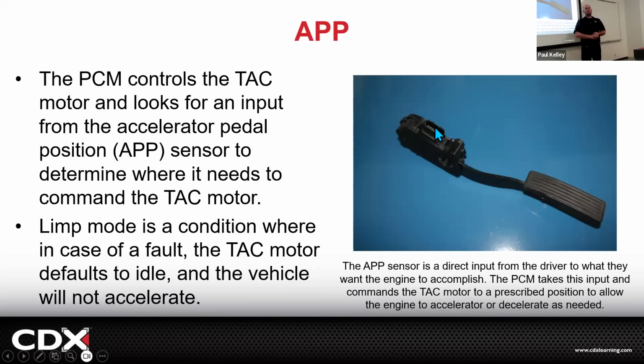Typically you'll have a sensor that goes from about half a volt to 4.5 volts, and another sensor that goes from about 4.5 down to 0.5. They should read different numbers, but those numbers should always check out against each other. So if you're at 10% throttle, maybe that's 4.2 volts and 0.8 volts. If those 2 voltage readings are accurate, the ECM sees that and says that sensor's working good.